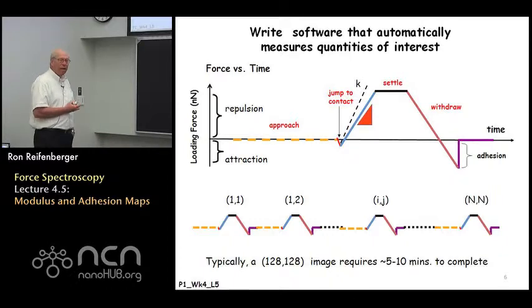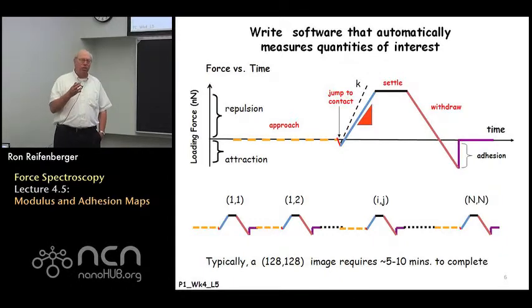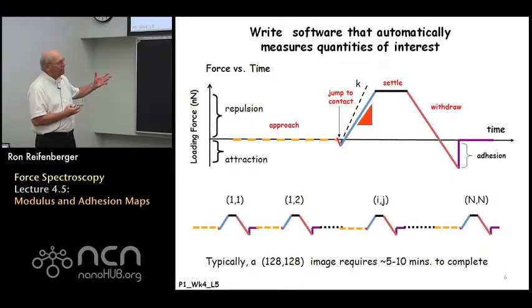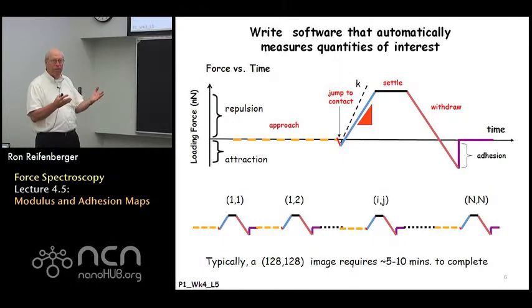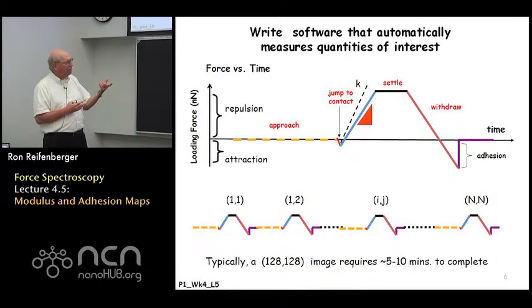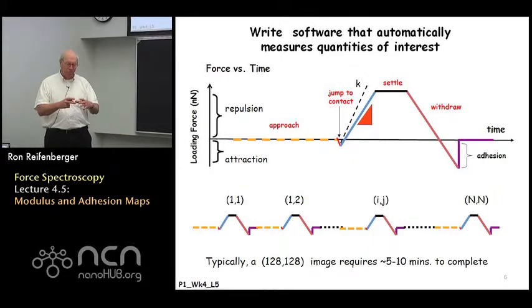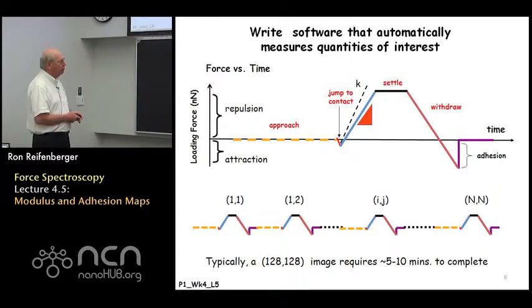Typically when you do an adhesion map or a modulus map, you do not perform it at the same resolution as the topographic map, simply because of the time required. Typically an adhesion or modulus map contains something on the order of 128 by 128 pixels, and acquiring an image at that resolution typically requires five to ten minutes. This means during the experiment you need a very stable situation — you can't have a lot of thermal drift, so you need to warm your system up and let everything stabilize to get reliable data.